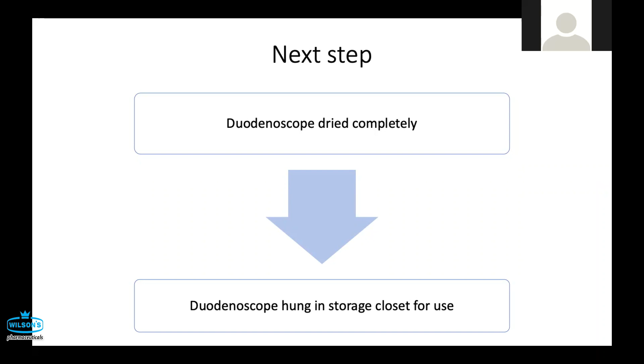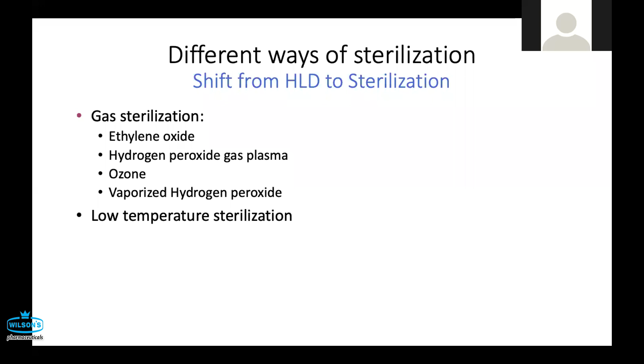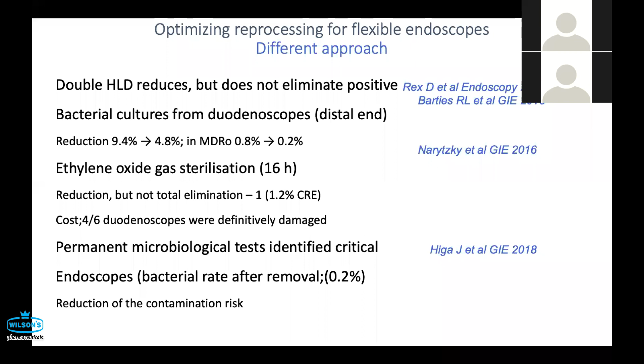So after we talk about manual cleaning and disinfection, can we shift on to sterilization? And these are the various methods of sterilization. Ethylene oxide, ETO, we know, but the problem with all these methods is that they cause damage to the scope. If you look at this, 4 out of 6 duodenoscopes were definitely damaged in this study in 2016. So you have to find safe ways to sterilize, but that also cannot take the place of the manual cleaning, which is very essential.